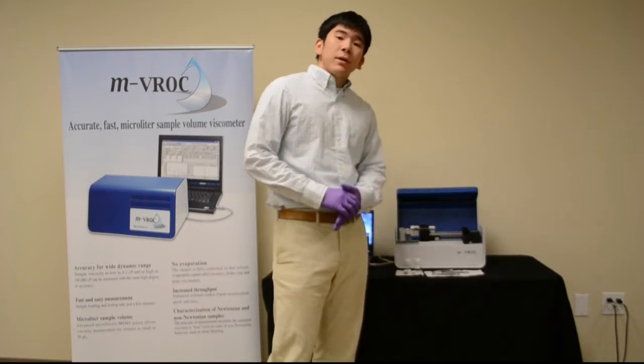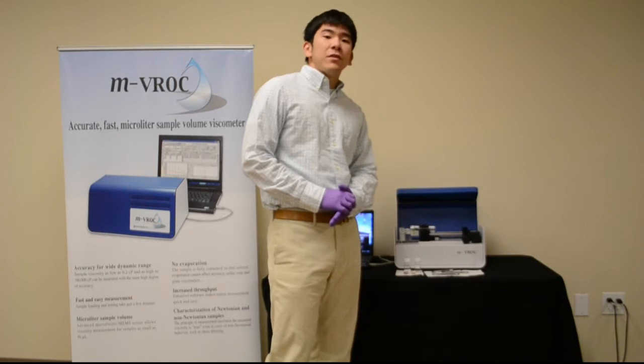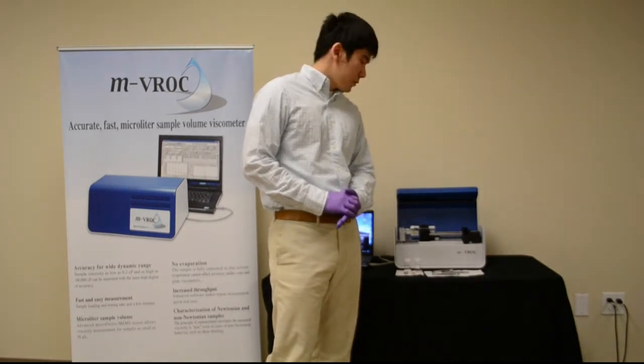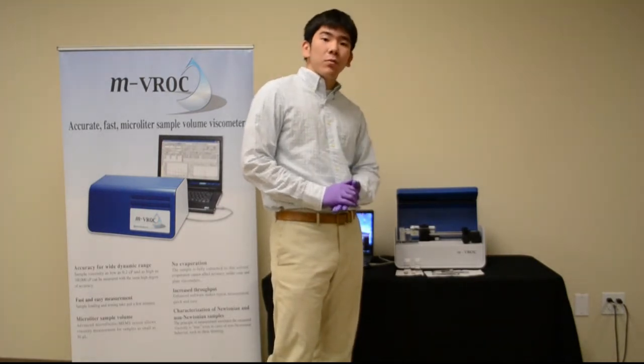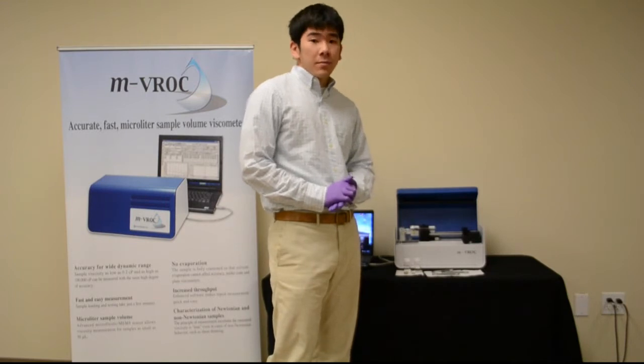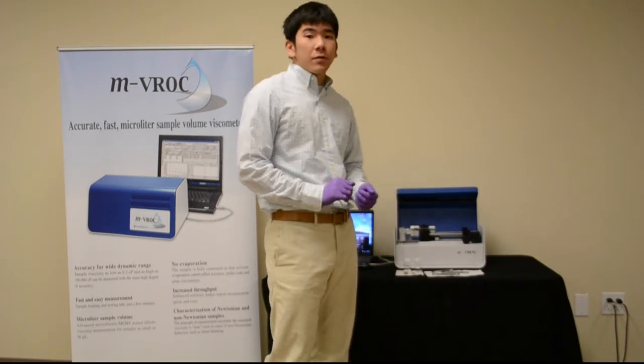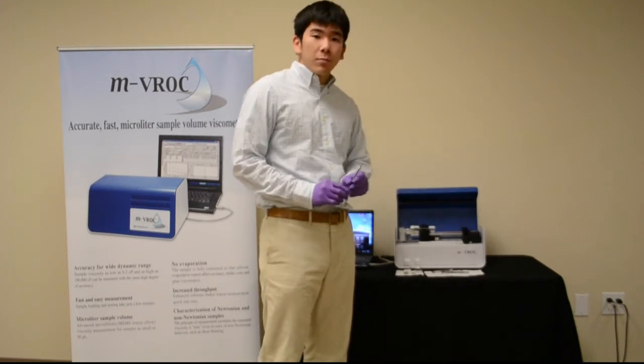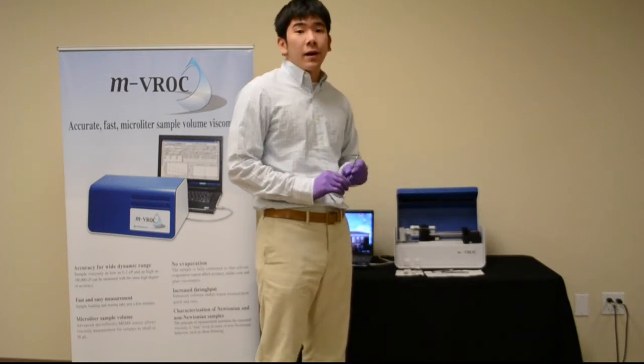And in order to get precise and accurate measurement, the syringes need to be absolutely clean. In order to do that, we recommend the customers to rinse their syringe with isopropanol and to dry them with air duster.